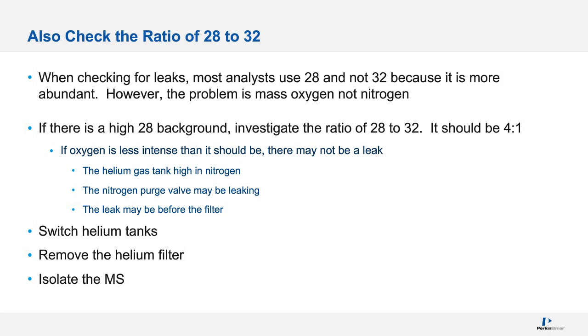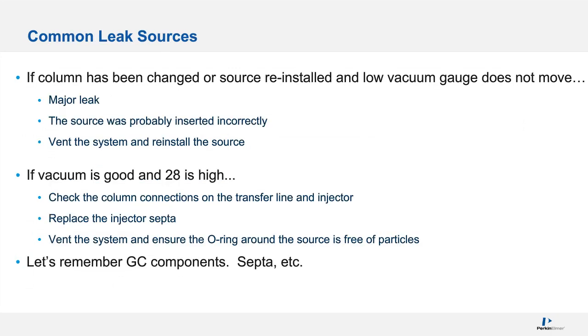Okay. Let me see if there's anything. Okay, there's nothing new. Oh, the O-ring on the inlet. Well, that's not really going to leak. But the O-ring on your source may be leaking. It may have gotten distorted. The inlet O-ring, usually this would not happen to, but especially if you took it out and put it back, a mistake may have happened.